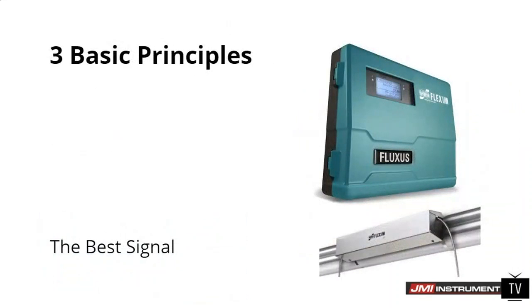So when we look at the signal, the main diagnostic we look at for gas measurement is SCNR. That is the amount of signal that we're getting through the gas versus the amount of noise that we're putting on the pipe. So it's a correlated noise ratio, which means it's in the same frequency band, and it's actually noise that we're putting on the pipe.